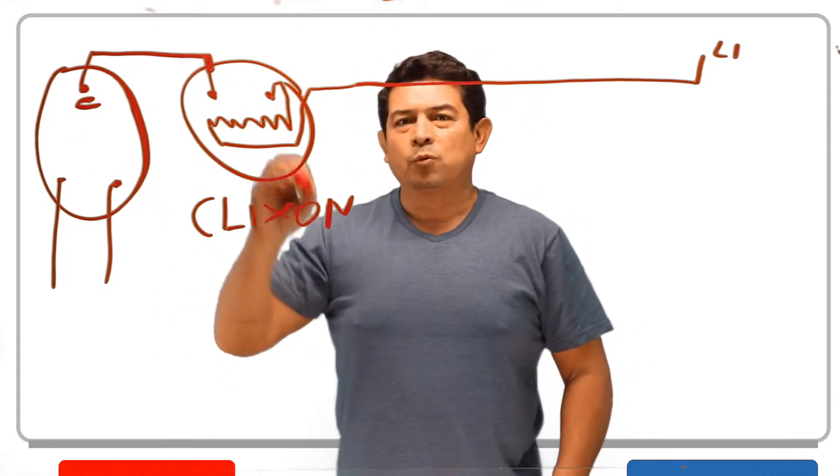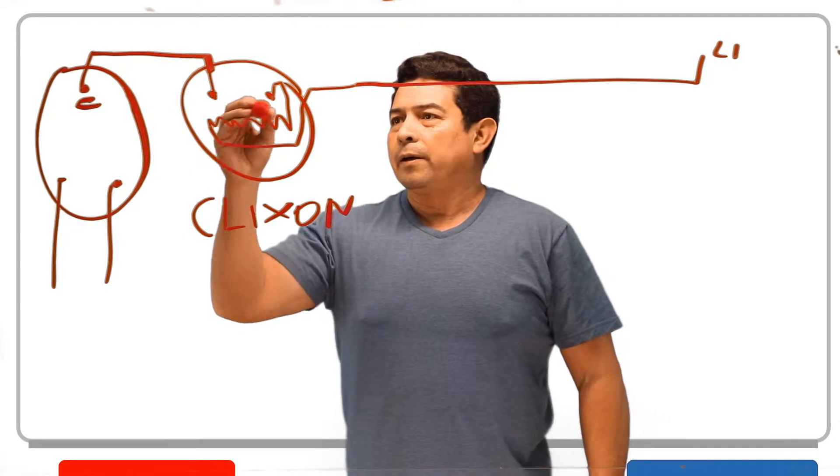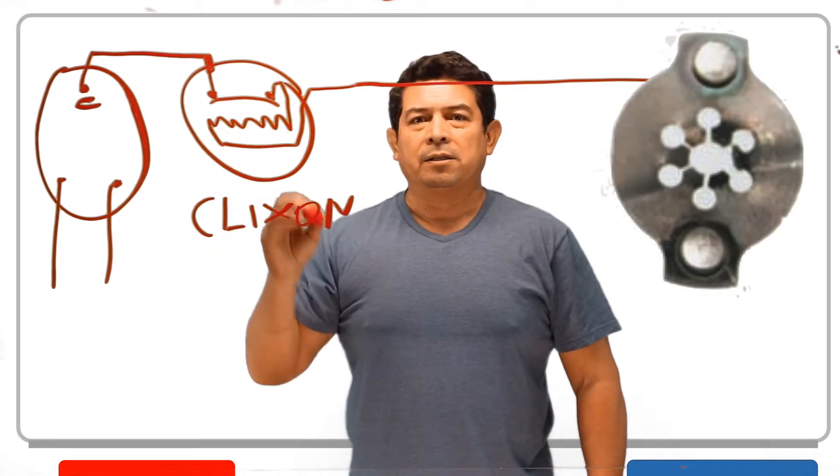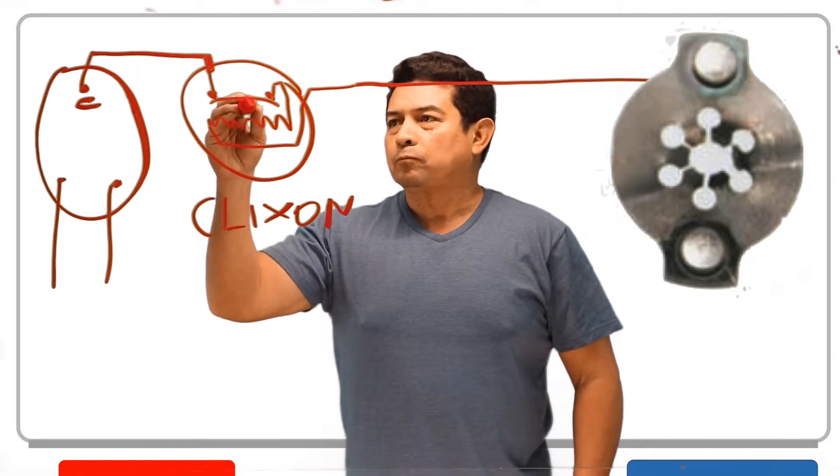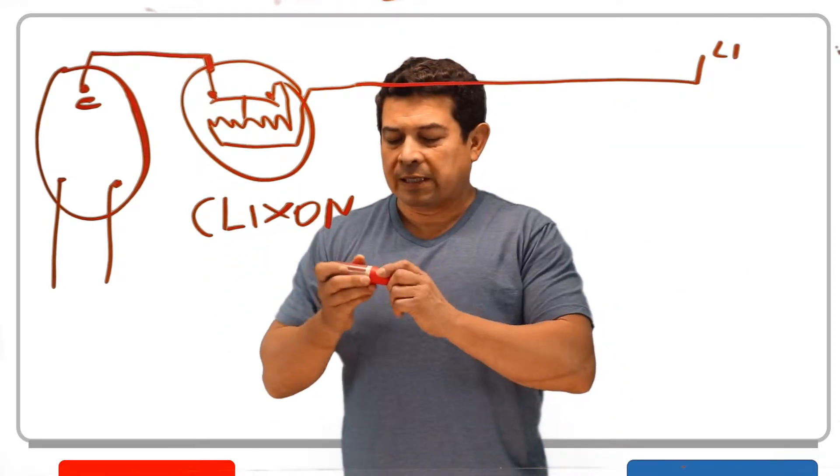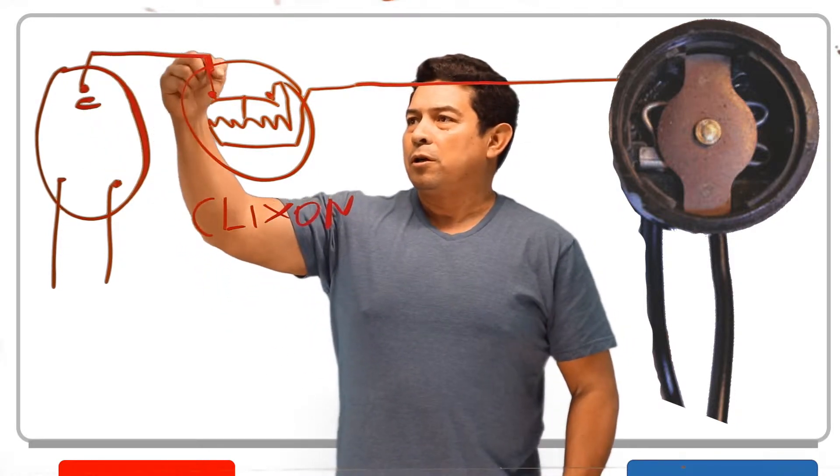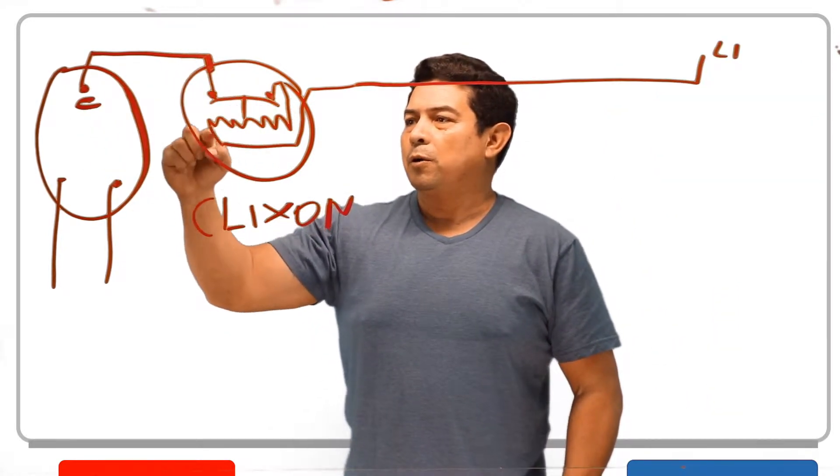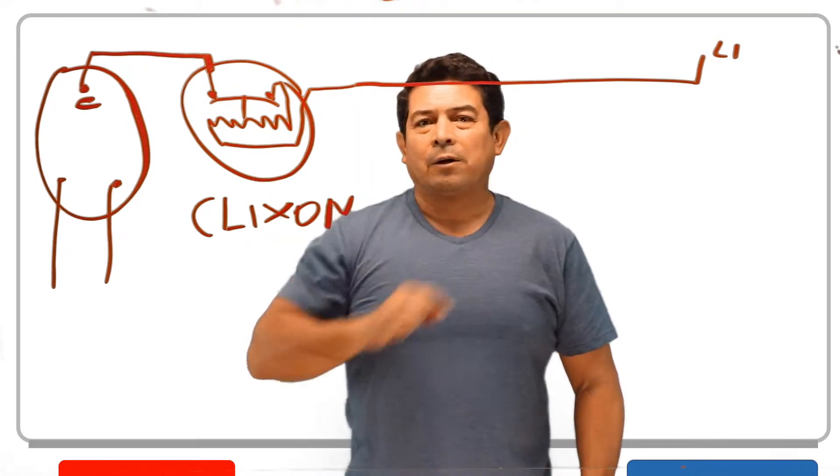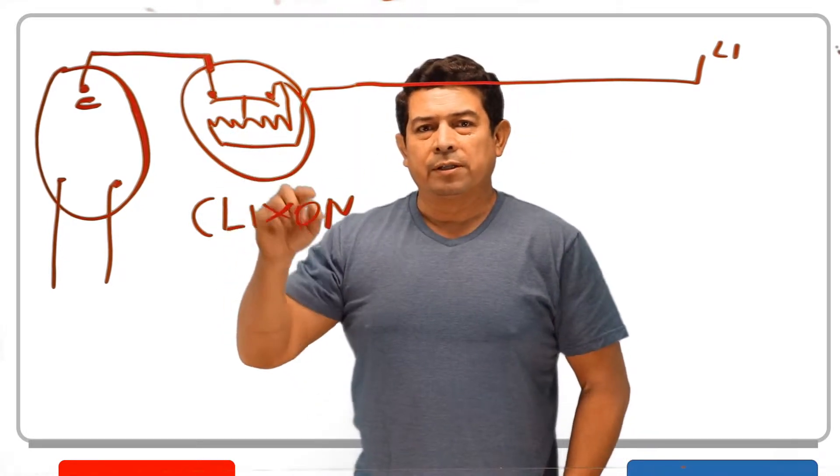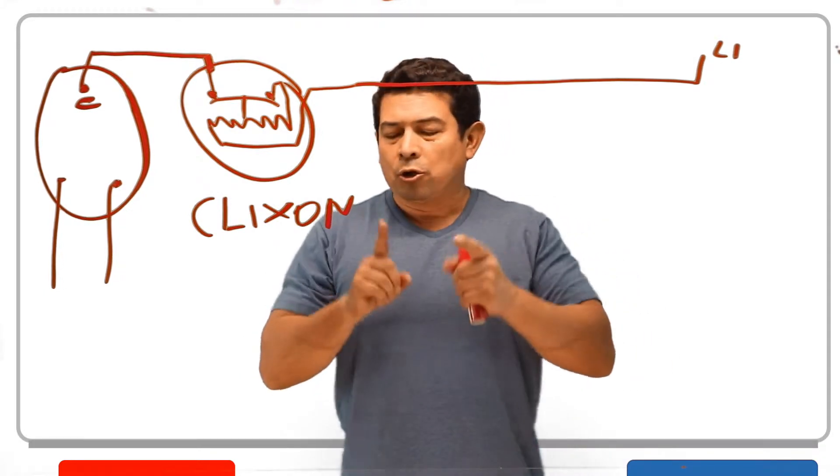But let's talk about this one because this is where the Klixon would be. Now on here, there is a bimetallic disc like this. All of this is inside of that little black piece and what happens is as the amperage goes through here, it goes through that little heater and then back on out. What happens there is as the amperage increases, anytime amperage increases, two things change.